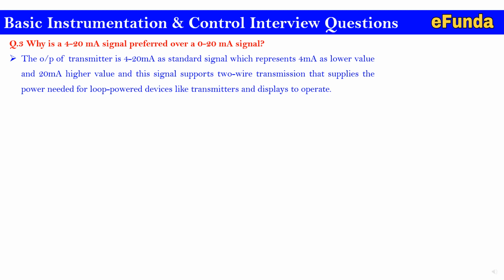The output of a transmitter is a 4 to 20 milliamp standard signal, which represents 4 milliamp as the lower value and 20 milliamp as the higher value. This signal supports two-wire transmission that supplies the power needed for loop-powered devices like the transmitter and the display to operate.